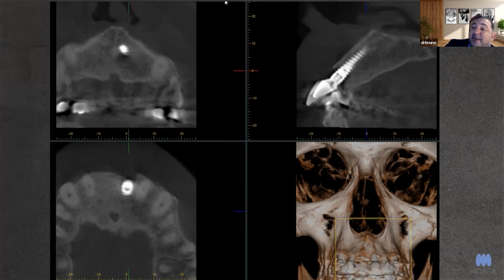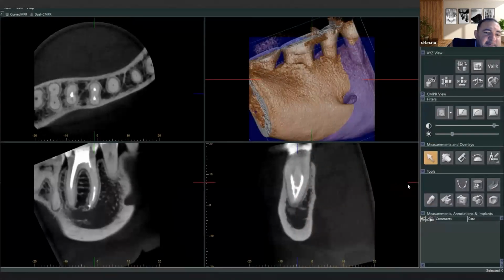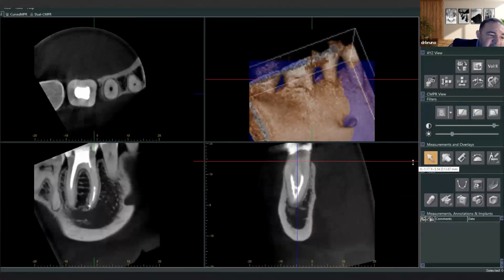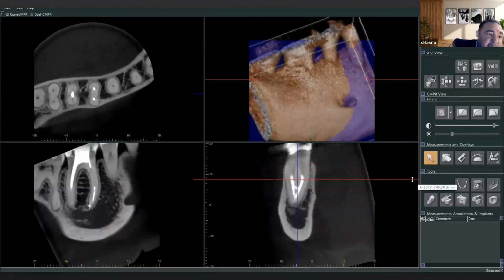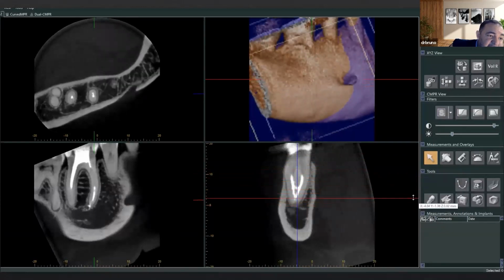So one more time, if you have an X800 within your practice, avoid using the 9x8 whenever you have to deal with artifacts, and use the 8x8 scan with the HD module at 17 seconds acquisition. That will increase your resolution substantially and decrease the amount of artifacts substantially related to dental implants and crowns. Again, that's when you get those beautiful scans with endo, high KV, high MA, all right?